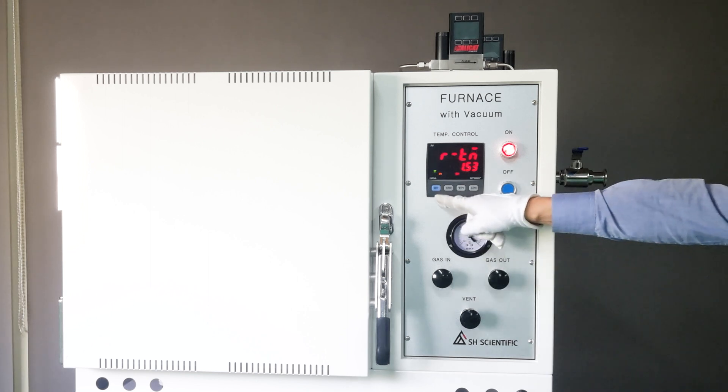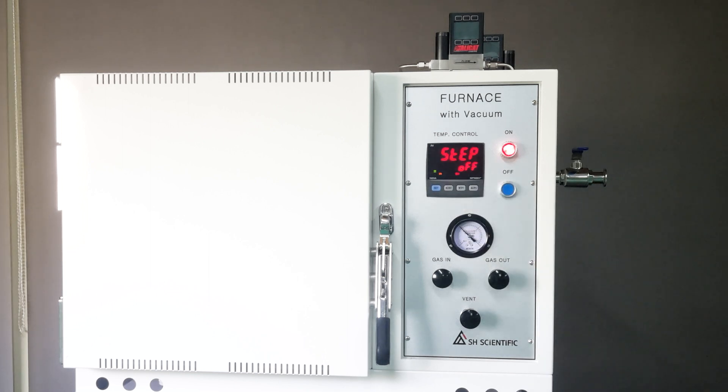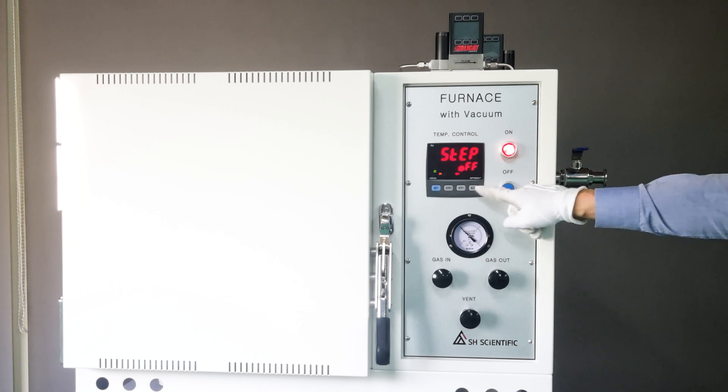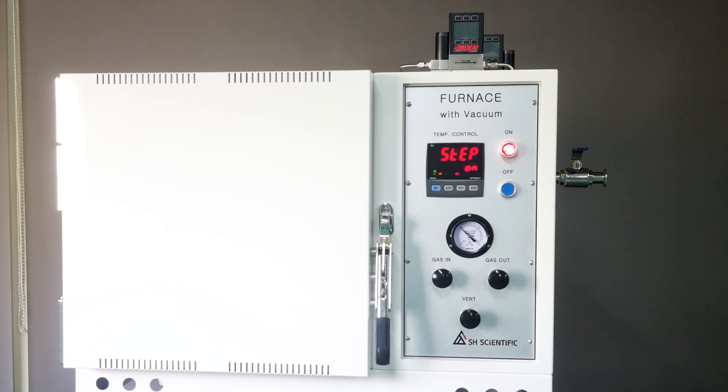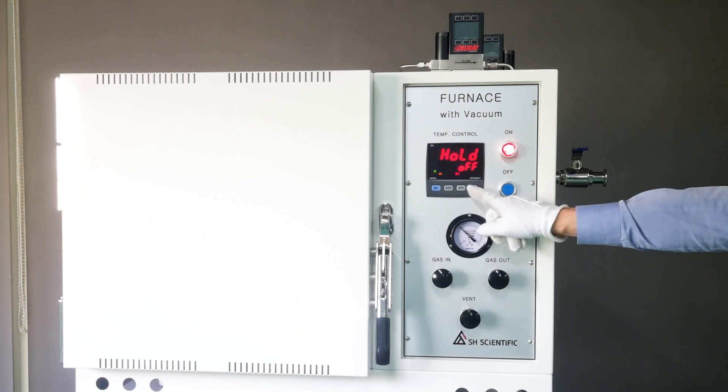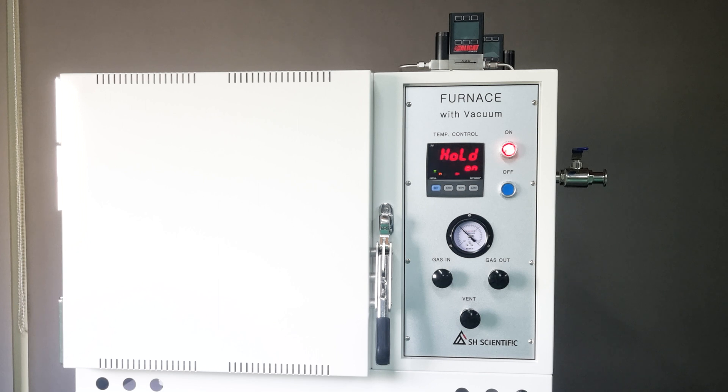Finally, two other things to note. Step Off is a default setting. If you change it to Step On during operation, it will skip the current step and force it to jump to the next step. Hold Off is also a default setting. If you change it to Hold On during the operation, then it will hold the current step indefinitely, or until you turn the furnace off. Keep it in mind.